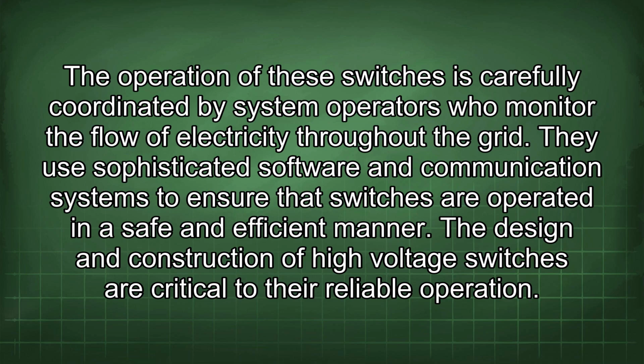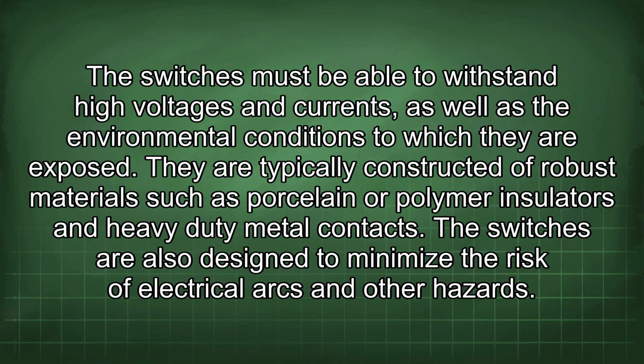The design and construction of high voltage switches are critical to their reliable operation. The switches must be able to withstand high voltages and currents, as well as the environmental conditions to which they are exposed. They are typically constructed of robust materials such as porcelain or polymer insulators and heavy-duty metal contacts. The switches are also designed to minimize the risk of electrical arcs and other hazards.